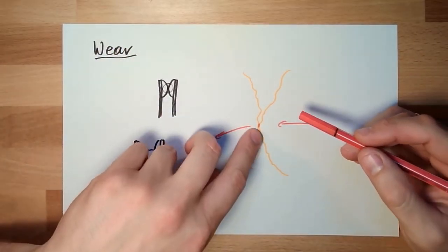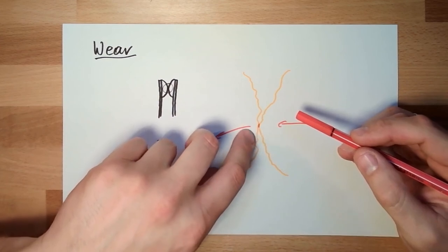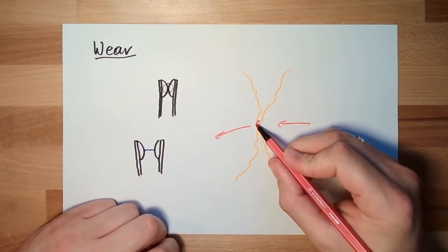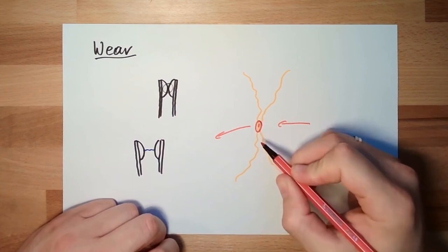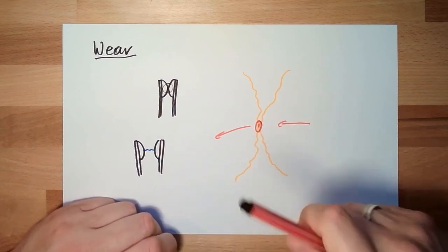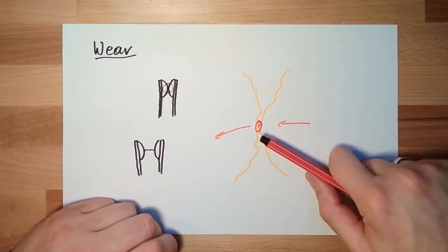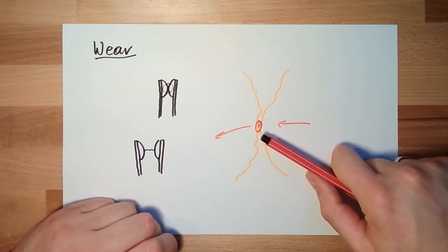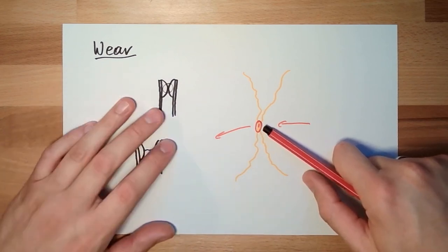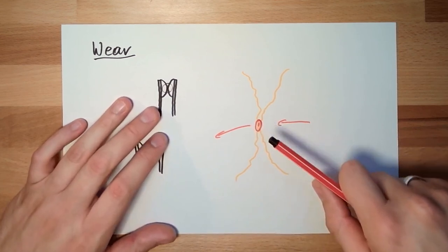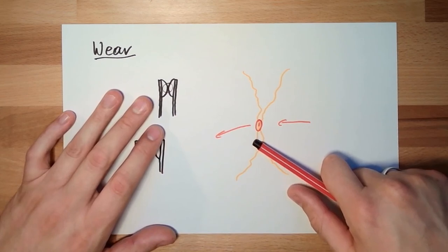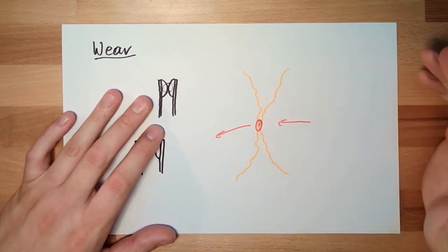And even if you press the current through this small hole, let's say, or this small contact point, then it might get very, very hot in here. It might get so hot that it's melting, and then you have a bigger contact point because this is liquid. Then it's cooling, and that is called welding. Connecting two parts by melting them, we weld them. We just welded together our contacts, and if we now want to open it, it is not working, it is not switching. The contact stuck to the other. Actually, it's welded. In German, we say Kontakt klebt. It sticks.